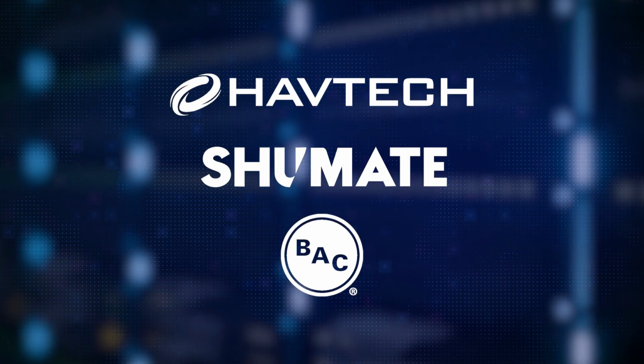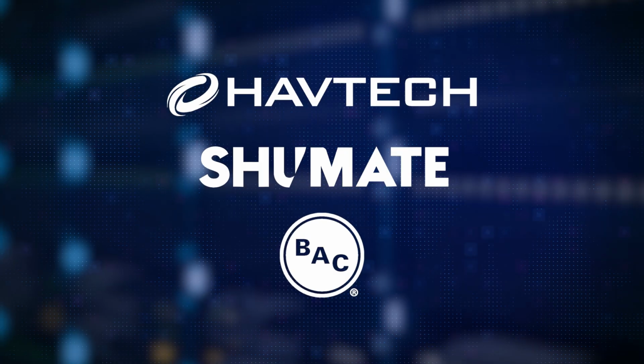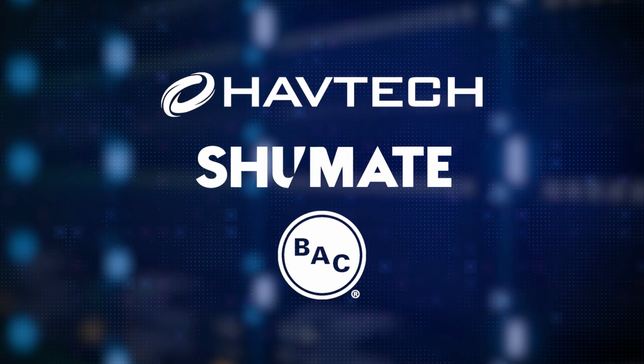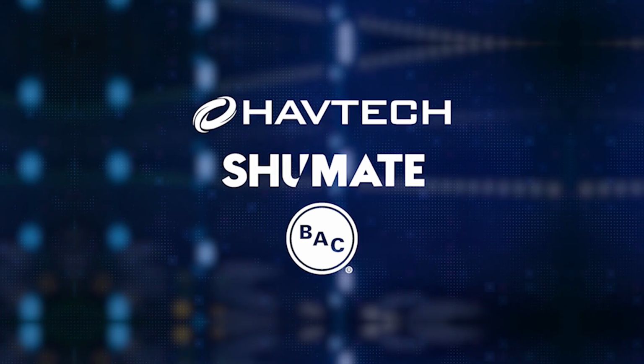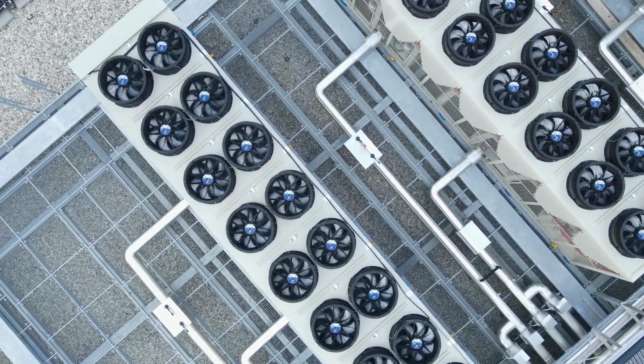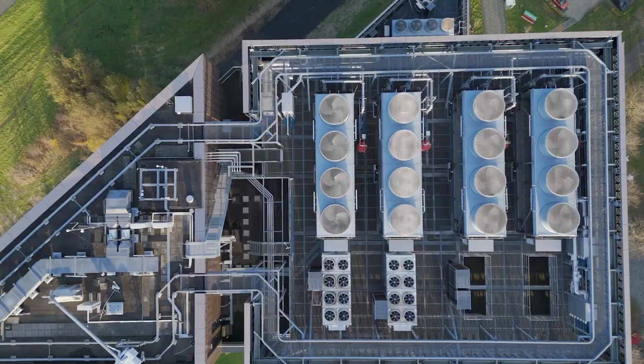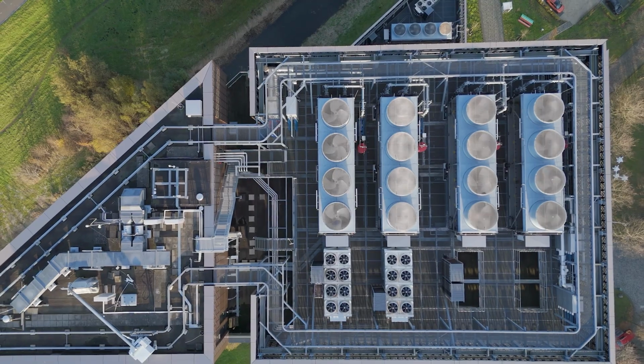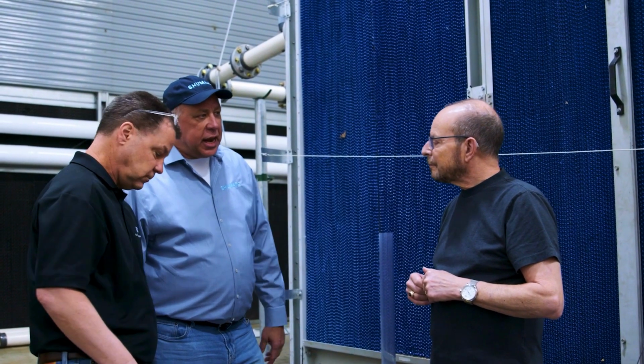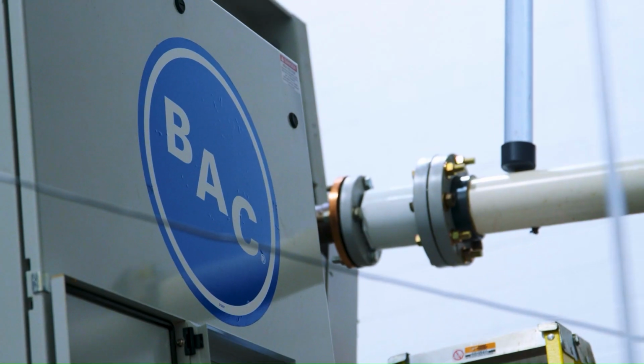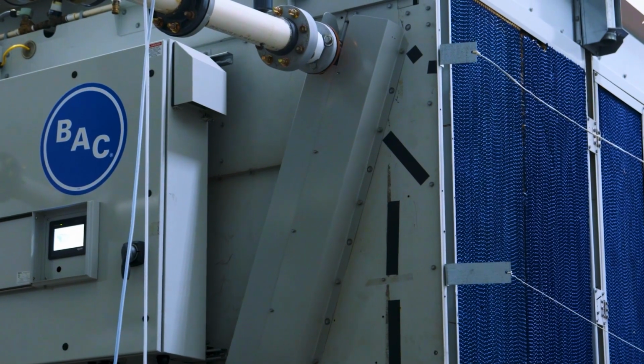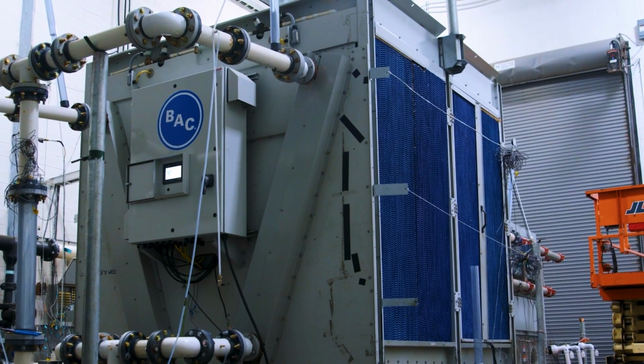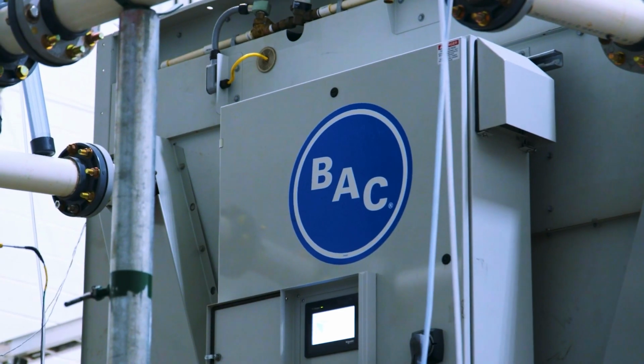That question brought Havtech, Shumate Engineering, and BAC together to develop and validate a different path forward for direct-to-chip data center cooling. Shumate recognized the potential to eliminate air-cooled chillers and cooling towers in favor of a single chilled water loop built around an adiabatic cooler. The challenge was identifying a system capable of meeting the extreme operating requirements of the application. Havtech brought BAC to the table. The BAC Trillium Series hybrid adiabatic system offers a compelling solution.